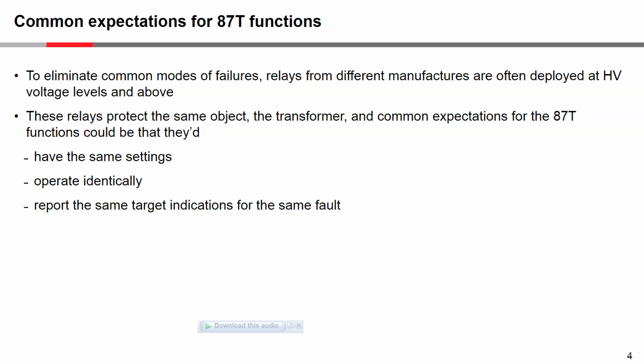If you're now talking about protecting a transformer, a common expectation on the part of the protection engineer applying the two different transformer protection relays from the two different manufacturers could be that they have the same settings. It's the same transformer, so the expectation could be that these two relays should have the same settings, that they should operate identically, and if they operate correctly, they should report the same target indications for the same fault. That, I believe, could be the common expectation from the utility protection engineer who's applying the transformer protection relays.